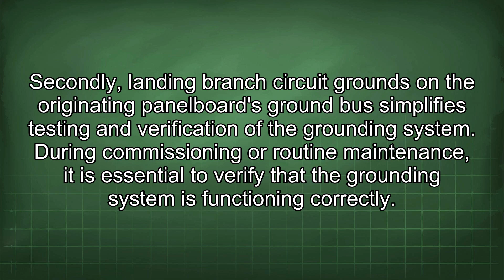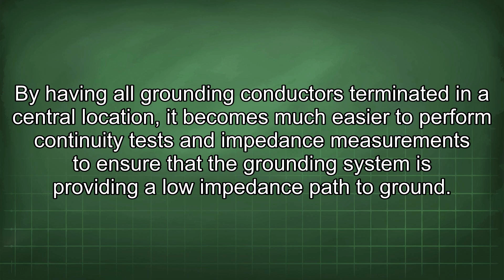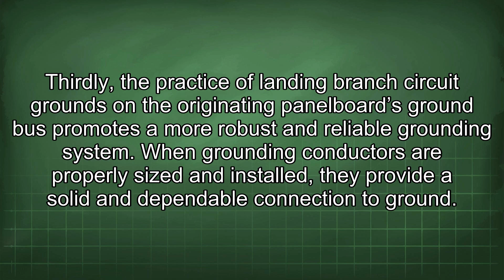By having all grounding conductors terminated in a central location, it becomes much easier to perform continuity tests and impedance measurements to ensure that the grounding system is providing a low impedance path to ground. Thirdly, the practice of landing branch circuit grounds at the originating panel board's ground bus promotes a more robust and reliable grounding system. When grounding conductors are properly sized and installed, they provide a solid and dependable connection to ground.